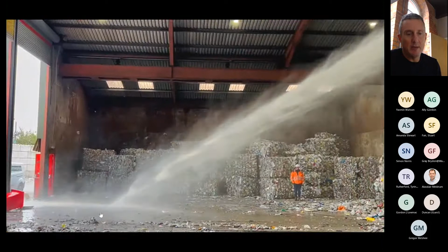The camera system now checks for any further hotspots, to see if the fire has been dealt with. Yes, it has, so it automatically goes into shutdown. Meanwhile the camera scans the rest of the building for any other fires. Should it detect another fire, it will move the cannon to that position. Camera's happy, fire's out, the system stops, and then the system drains down.